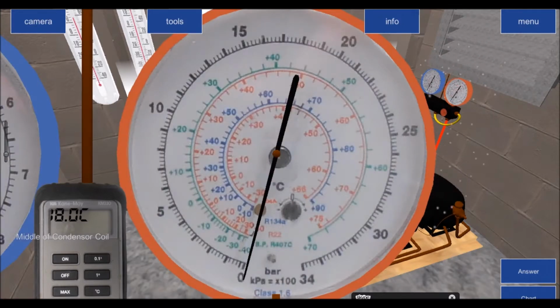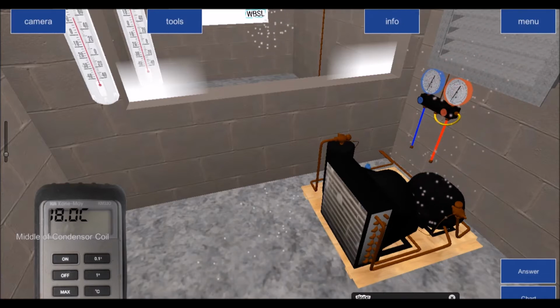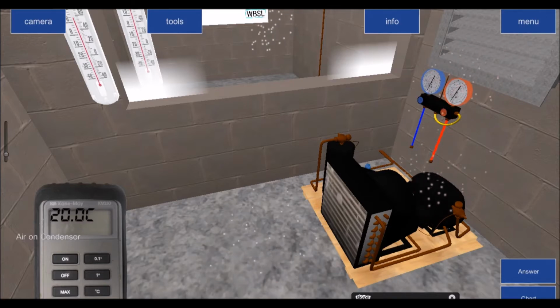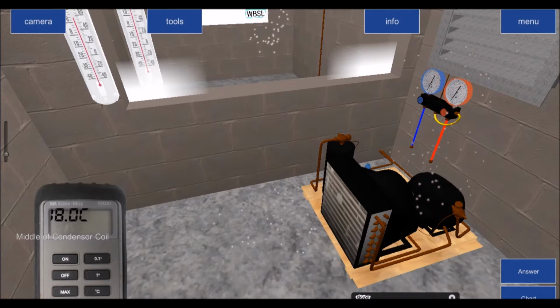So if that was at 15 bar, in actual fact, if we look at 18 degrees, our head pressure would be, so there's 10, 12, 14, 16, 18 and 20. You can go across here and you can see that it's just above 9. It's about 9.1 bar pressure at 18 degrees. And remember, our normal operation was up at 15 bar, so there's something wrong here. But anyway, what we're saying is, how do I know that a condensing temperature of 18 degrees for an air on temperature of 20 degrees is normal? And then, how do I know what my subcooling value should be?